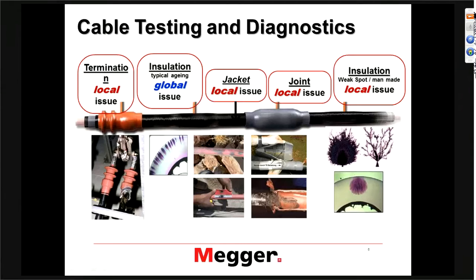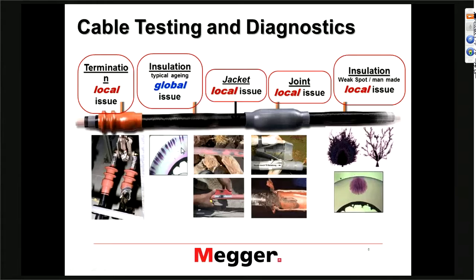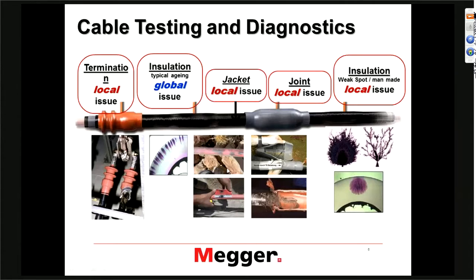Here you see terminations — one good, one bad. On the global aging of the insulation, you see a very consistent number of water trees, and especially the size of these water trees is very consistent. That is a typical aging condition of an XLPE cable. The jacket shown here happened to be a wind farm cable — on the bottom photo you can see it blew right through the insulation.